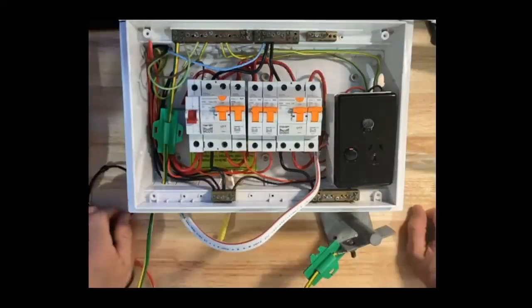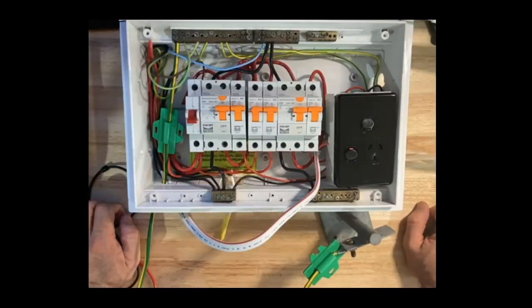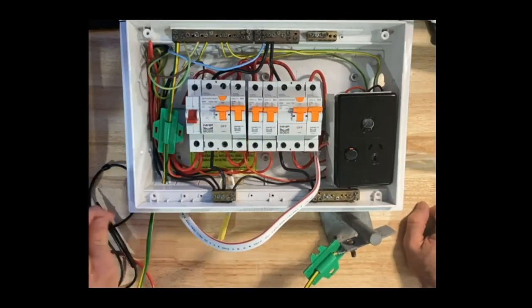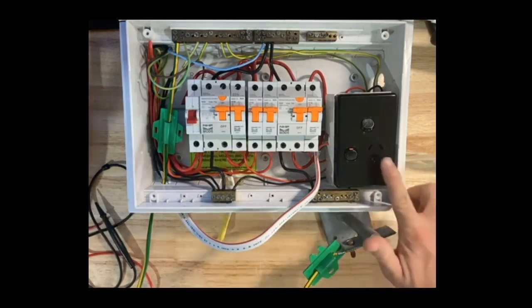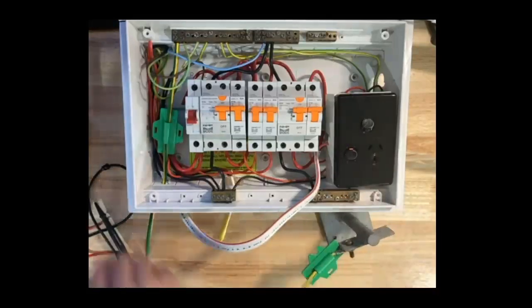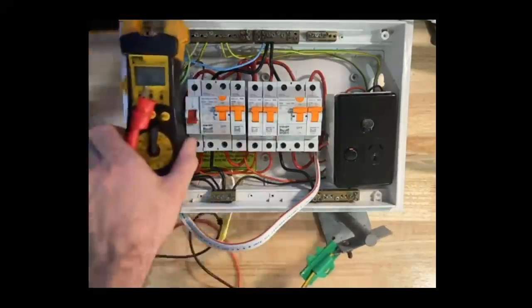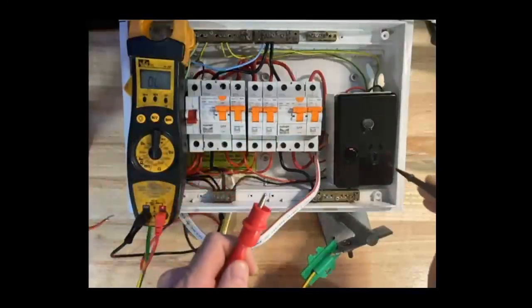Okay, so the next test we would then do is earth bonding conductors. I don't have any bonding conductors here, but if you have installed bonding conductors in your installation, again to water pipes, steel benches, anything like that, now we would test those. And the third test we do is the earthing conductor here. Now, if I wanted to do this test on this particular switchboard, that would be very easy.